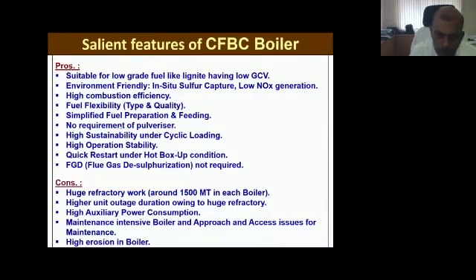There is no requirement of pulverizers, but for limestone, which is being added as an additive, we need pulverizers. We have 3 pulverizers. The particle size is almost like the pulverizers used in a normal conventional power plant, and 75 micron size limestone is added with the lignite for capturing sulfur inside the boiler. This boiler has the advantage of high sustainability under cyclic loading because of the maximum heat storage. High operational stability means even if there is a fuel cut out for 10-15 minutes, we can support the operation, because the refractory and the bed material in the boiler store heat for almost 15-20 minutes of operation. Quick restart under hot box up condition is also helped because there is high heat storage inside the combustor.